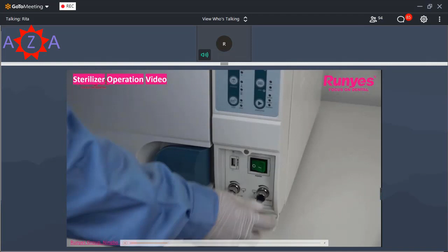There is no sound, but I will explain. So this is our model LED type 23 liter, with the accessories in the chamber: the rack, trays, USB, and the spanners and pipes. Firstly, we need to make sure the front foot peg is higher than the back side, like this, to ensure the condenser water drains off. Also, leave gaps on each side so the machine has room for its fans.